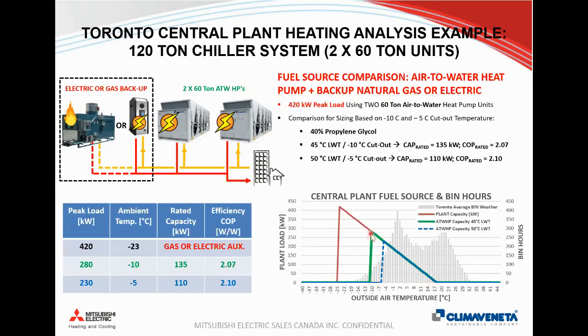We're going to look at using two heat pumps that's basically serving the system in this green triangle here. And if we say 45 is a little bit too cold, 50 degrees is more reasonable to provide heating, we're also going to analyze that where we selected the same units, but rated them down to -5, which are giving 230 kilowatts at this value to meet this peak load. And then we're going to compare that to the big red triangle here, which is just an all gas or an all electric system. And then we're going to compare the ratings.